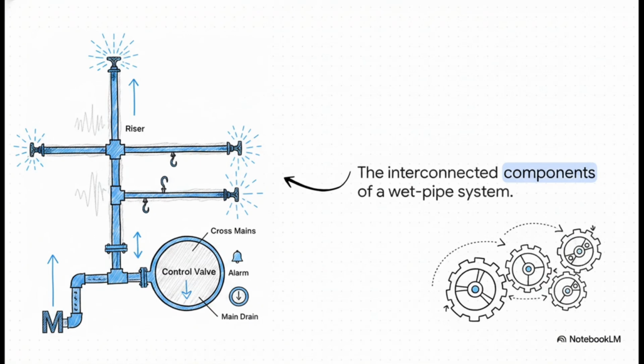So now we cut the network, but where is all this rushing water actually coming from? The anatomy of an automatic sprinkler system is incredibly systematic. Let's trace the journey of the water. It starts down at a municipal water main, pushing its way through a massive control valve. From there, it travels vertically up what's called the riser. That riser feeds horizontal pipes known as cross mains. Those cross mains then branch out further into, you guessed it, branch lines, which finally deliver the water right to the sprinkler heads. Along this whole journey, you're going to find alarm valves, main drains for maintenance, and a massive network of heavy-duty hangers and clamps securely supporting the decreasing pipe sizes all the way to the very end of the line.